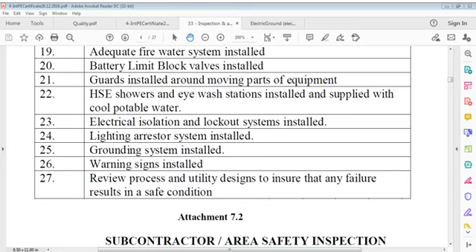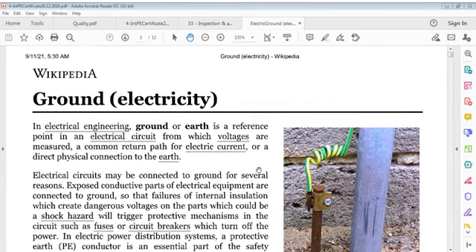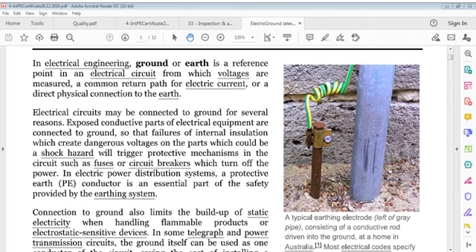These systems are there. We will just go through references, and this is from Wikipedia. It says, in electrical engineering, ground or earth, both are the same. It is a reference point from which voltages are measured, a common return path for electric current, or a direct physical connection to earth. Direct physical connection to earth, that's called earthing.